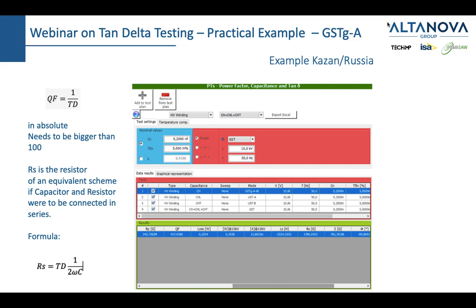Mr. Haris Hajj is asking, if a transformer has a tap changer, do we conduct the test with the tap in the nominal position, or does the tap have to be changed before the test? Actually, the tap is usually in the nominal, let's say the middle, position.